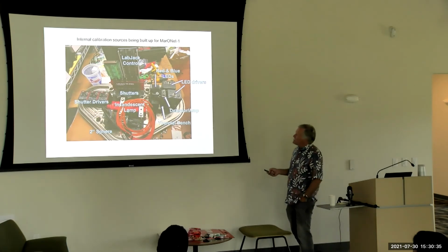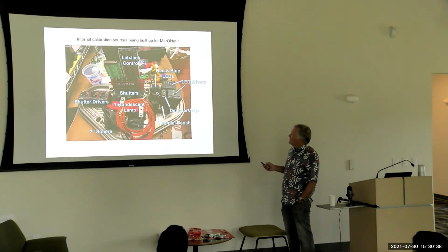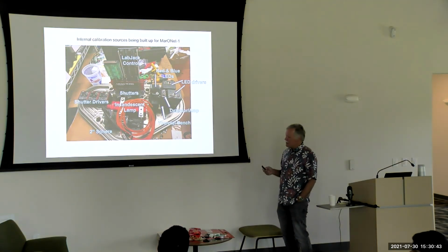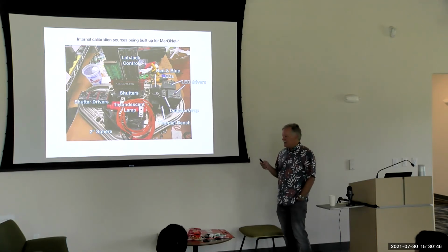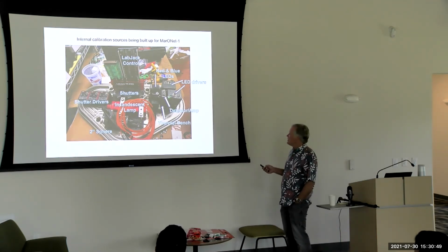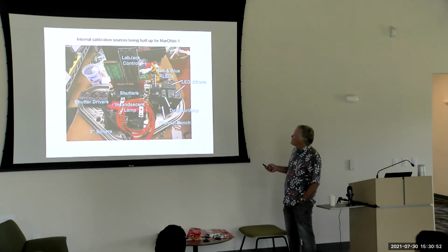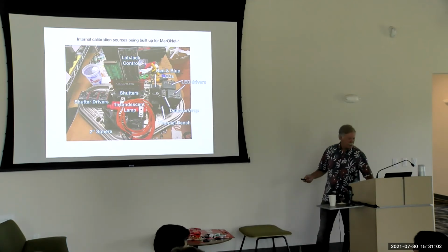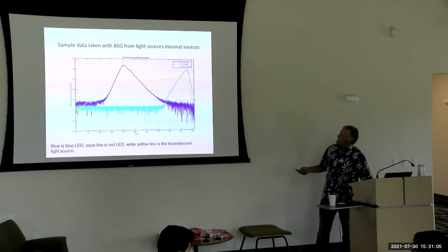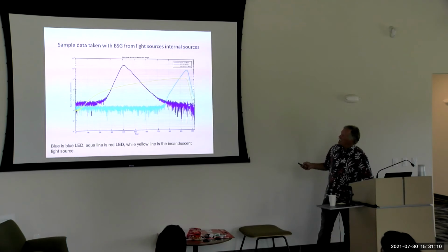Here's what it physically looks like. You have the red and the blue LEDs. They're on a thermal bench to try to maintain their temperature, because LEDs change their spectrum depending on their temperature, and also their intensity. There should be an incandescent lamp down in here. Here's your integrating sphere. All this stuff is inside the splitter housing, including a bunch of shutters. And here's some sample data taken with the blue LED and the incandescent lamp, and then the red LED. This is on the blue spectrograph looking at these sources.